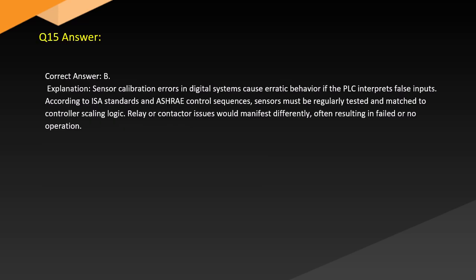Answer. Correct answer: B. Explanation. Sensor calibration errors in digital systems cause erratic behavior if the PLC interprets false inputs. According to ISA standards and ASHRAE control sequences, sensors must be regularly tested and matched to controller scaling logic. Relay or contactor issues would manifest differently, often resulting in failed or no operation.